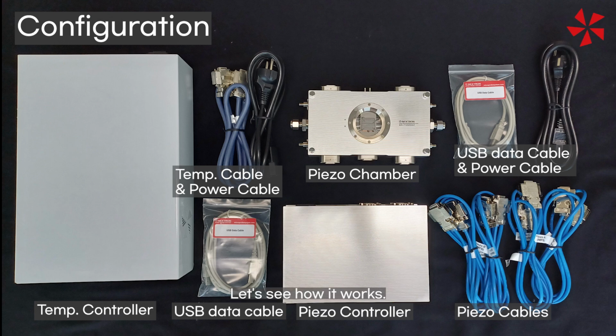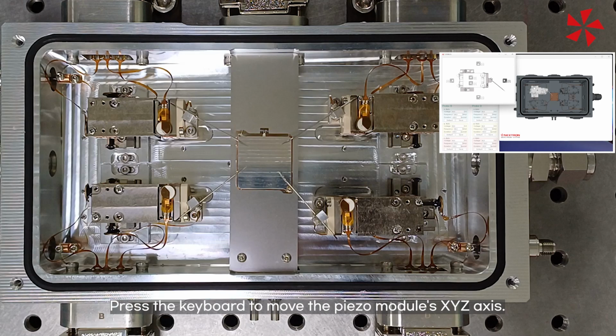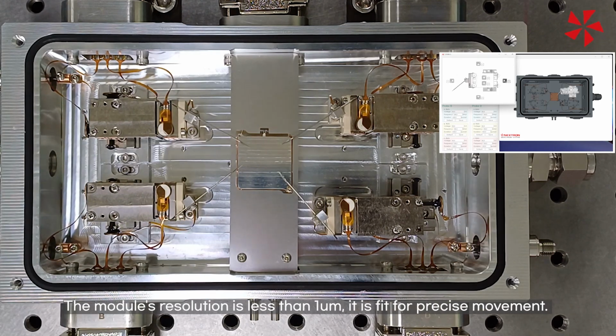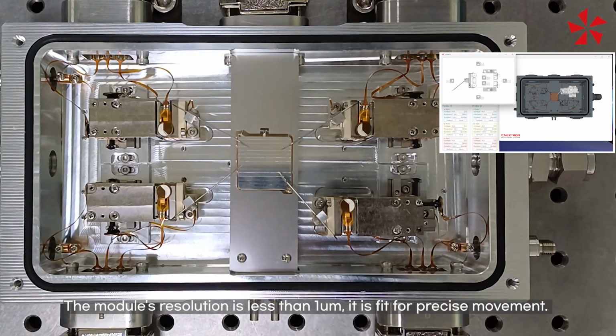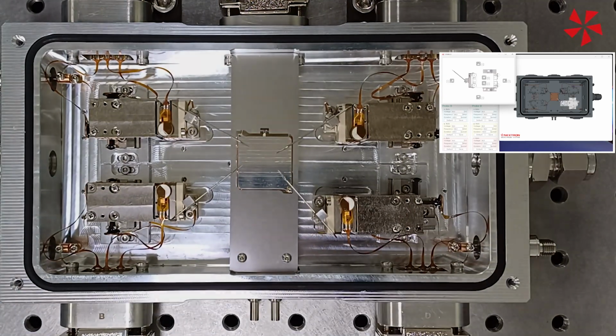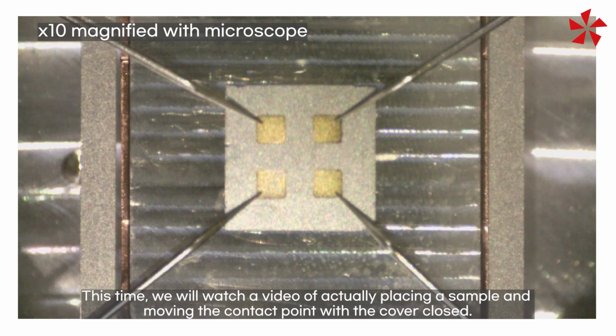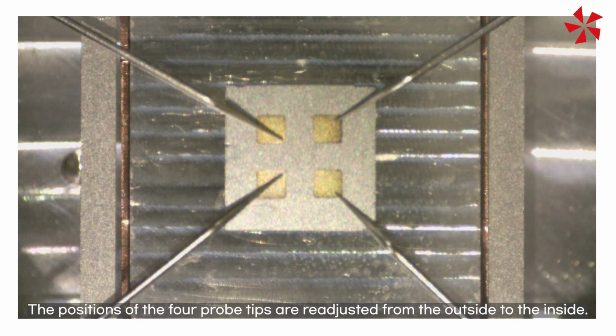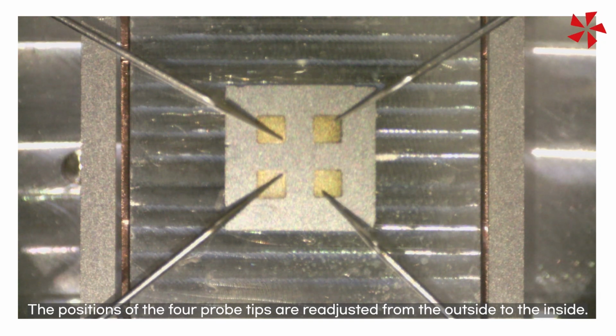Let's see how it works. Press the keyboard to move the Piezo Module's XYZ axis. The module's resolution is less than 1 micrometer. It is fit for precise movement. This time, we will watch a video of actually placing a sample and moving the contact point with the cover closed. The positions of the 4 probe tips are readjusted from the outside to the inside.